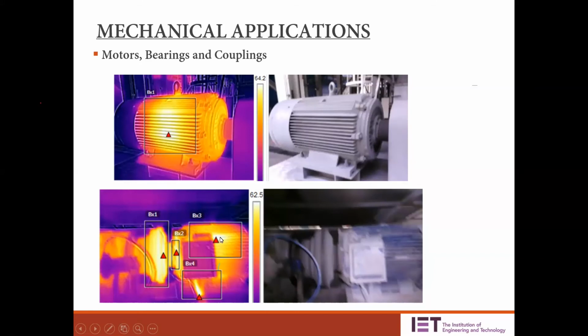As a rule of thumb, usually the motors, the windings, and the bearings must be low in temperature. So in this particular photograph, in the one on the bottom, you can see a hotspot, which is not supposed to happen. Upon inspection, we saw that this is due to an acute bending radius of the cable, which is surprising because an acute bending radius will reduce the current carrying capability of your conductor.